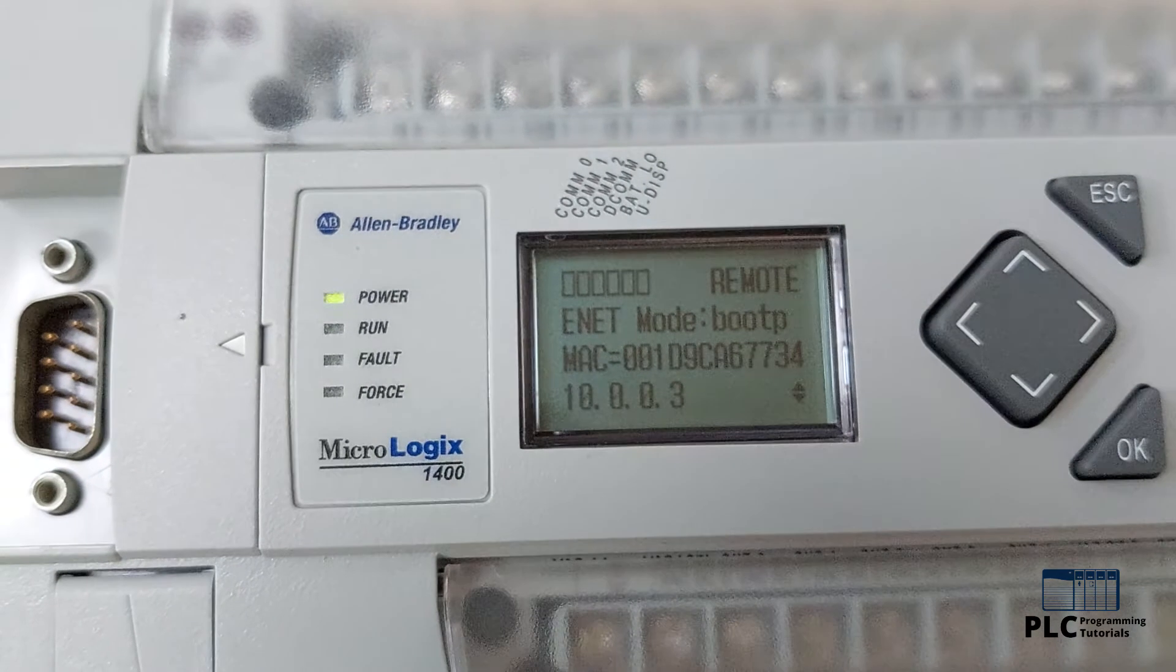As you can see, the PLC IP address is now set, but the PLC is still set to BootP mode. The problem with BootP mode is that the IP address will be reset every time we power cycle the PLC.